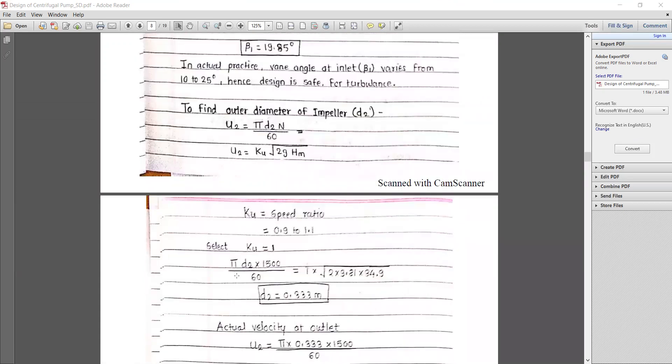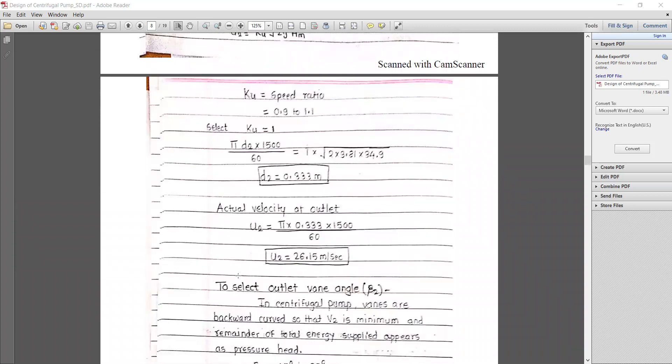To find the outer diameter of the impeller, u2 = πd2N/60, and u2 = ku × √(2gHm), where ku is the speed ratio ranging from 0.9 to 1.1 — we use ku = 1.0. Solving: πd2 × 1500/60 = 1.0 × √(2 × 9.81 × 34.9), giving outer impeller diameter d2 = 0.333 m.